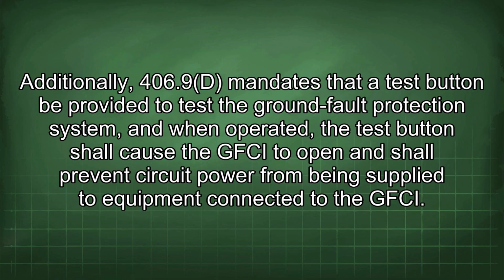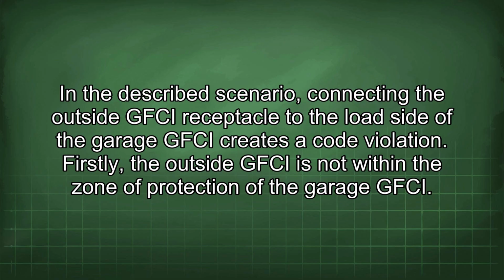Additionally, 406.9d mandates that a test button be provided to test the ground fault protection system, and when operated, the test button shall cause the GFCI to open and shall prevent circuit power from being supplied to equipment connected to the GFCI. In the described scenario, connecting the outside GFCI receptacle to the load side of the garage GFCI creates a code violation. Firstly, the outside GFCI is not within the zone of protection of the garage GFCI.